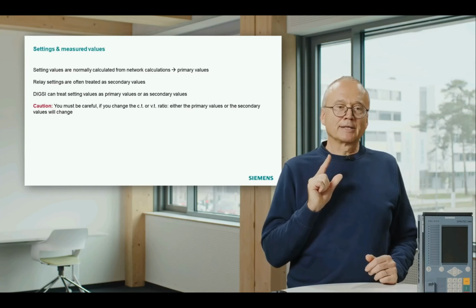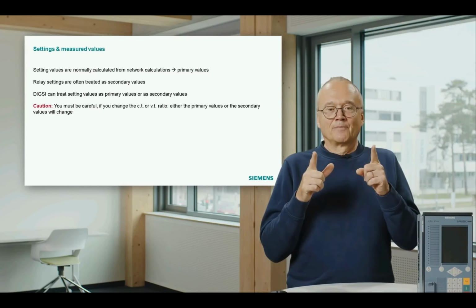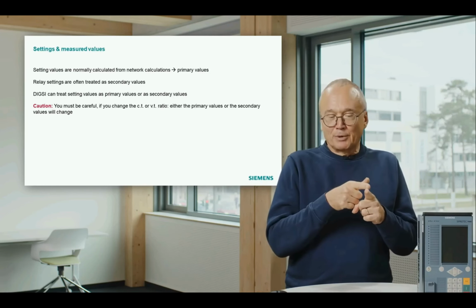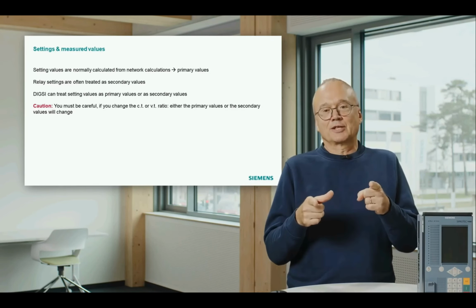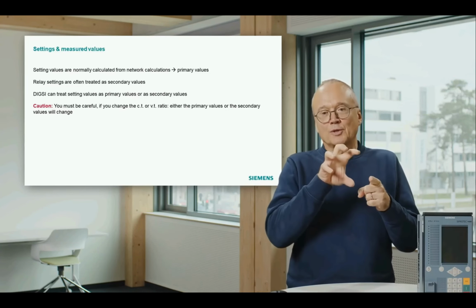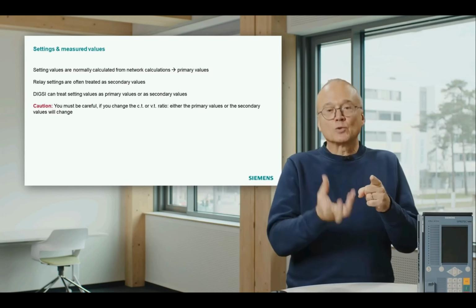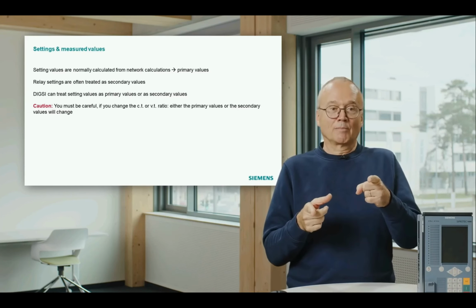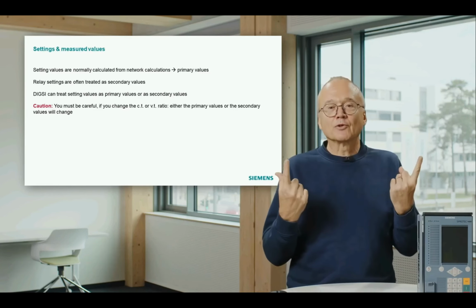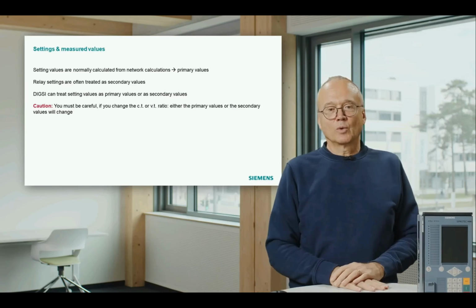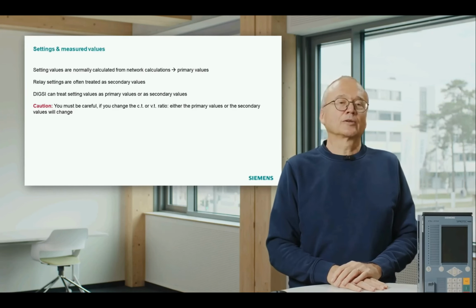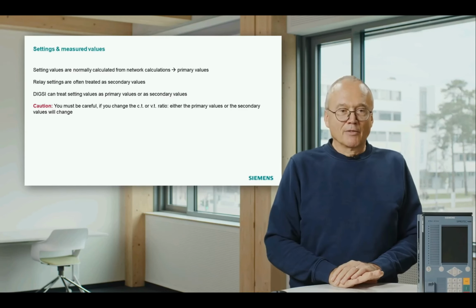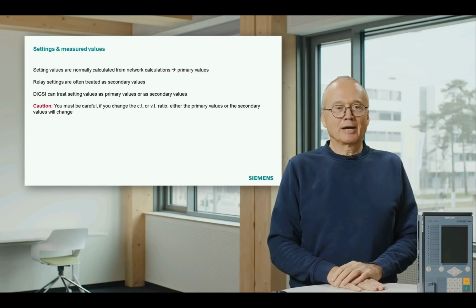Then you must make up your mind, because in this case, you have to change either the primary setting value or the secondary setting value, because they are connected with the ratio of the current transformer. And if you change that ratio, at least one of them has to change. And it must be very clear that you decide which one has to be changed and which one can remain constant. That was a short chapter about primary and secondary. And in the next chapter, we will start to build up a protection scheme for a feeder or a transformer feeder.